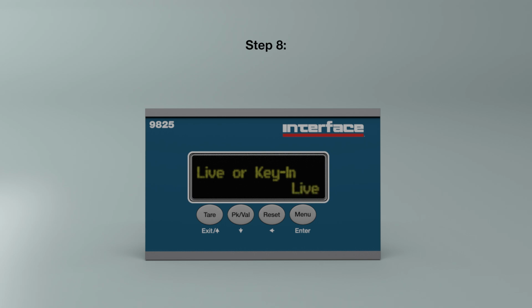For this example, we will be performing a live calibration. Press the reset key to toggle between the calibration methods until live is displayed. Press the menu key to confirm the selection. Step 9. After confirming the calibration method, the Live or Key-in menu item will be displayed again.